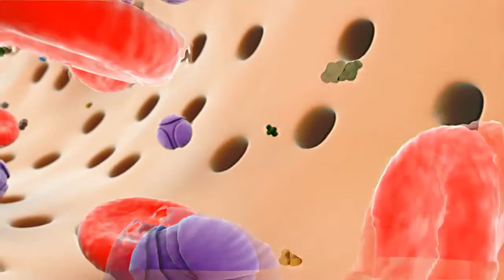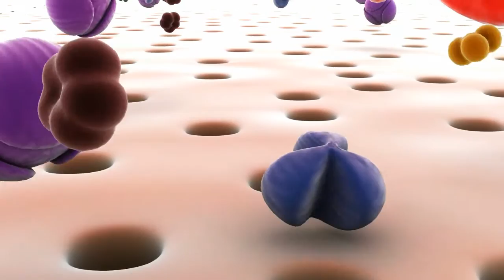The term flux refers to the permeability of the membrane in the dialyzer, across which accumulated toxins and excess fluid pass during hemodialysis. The low-flux cellulosic dialyzers could easily remove the smaller toxins, such as urea and creatinine, but larger molecules that are normally removed by normal kidneys were unable to fit through the pores.